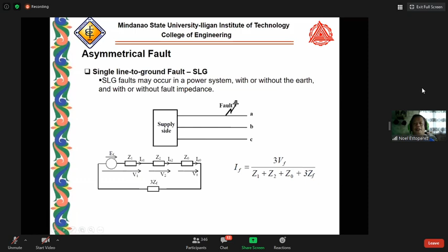Now, the fault current will be the sum of the sequence currents, so we combine IA1 plus IA2 plus IA0. Since they are equal, we get the factor of 3 here. So this is now the fault current for a single line to ground fault.